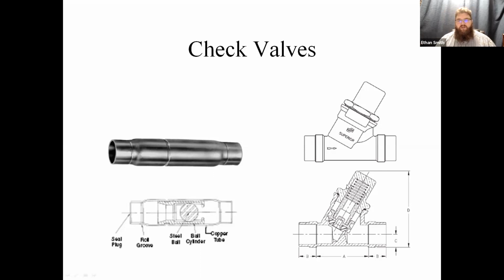Okay. Same thing with the spring checks. That temperature drop test applies as well. One advantage of these little ball checks is that these balls are made out of steel. These are usually in a vertical position, so you can actually take a magnet, put it on the outside of that housing, and pull the ball left and right, and you'll be able to feel it drag on that ball left and right. And in the vertical position, when you move that magnet away, you'll hear that ball click back down into the bottom. Obviously, you have to do that when the refrigerant isn't flowing, but that's one way to check those valves and make sure that that ball is free and clear.